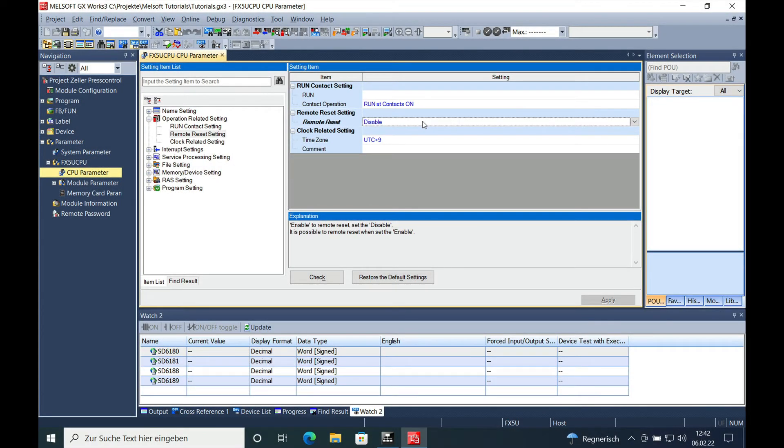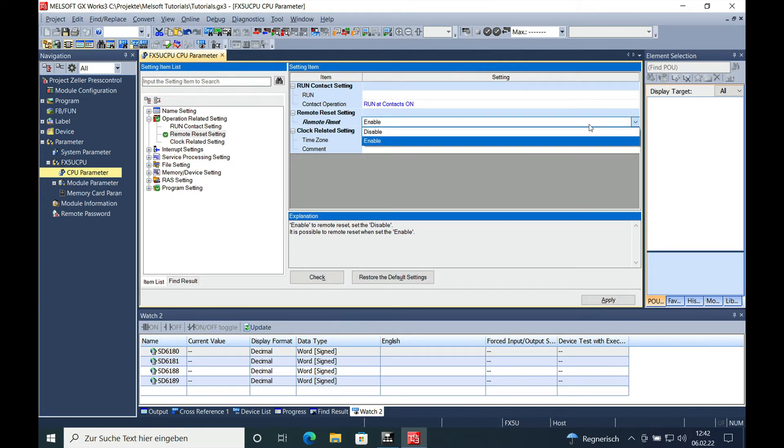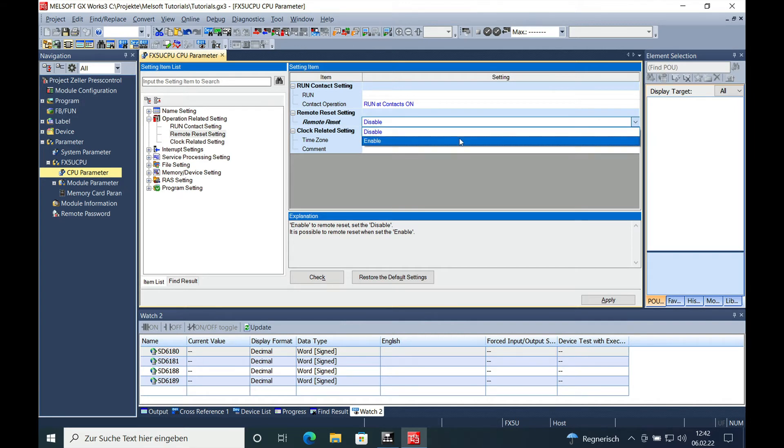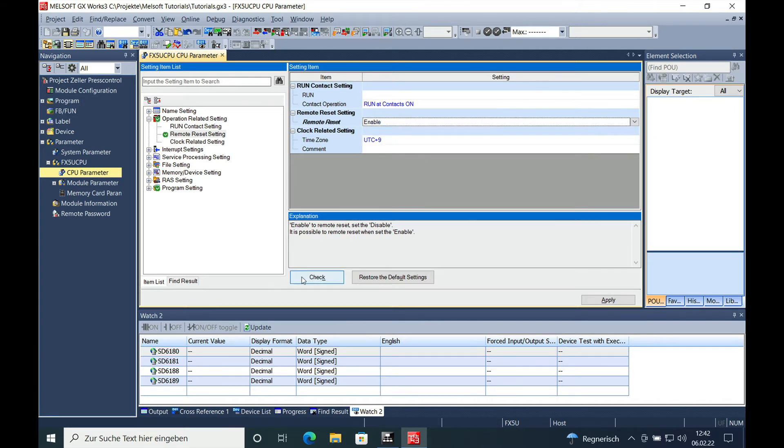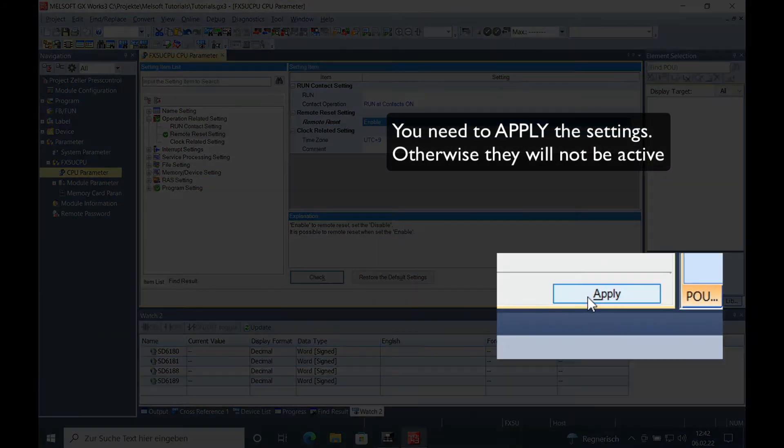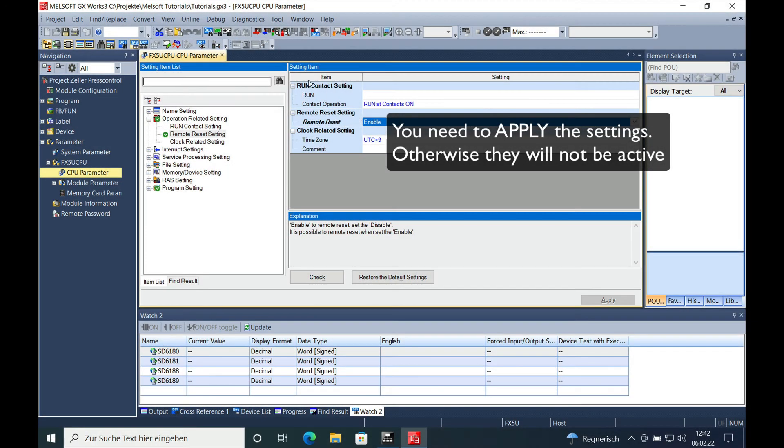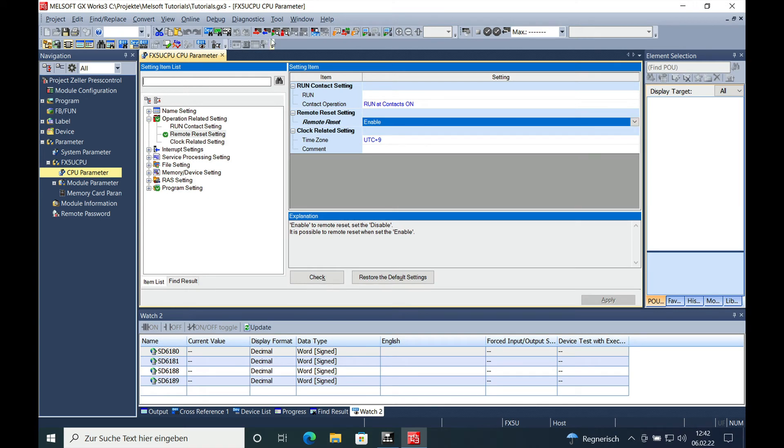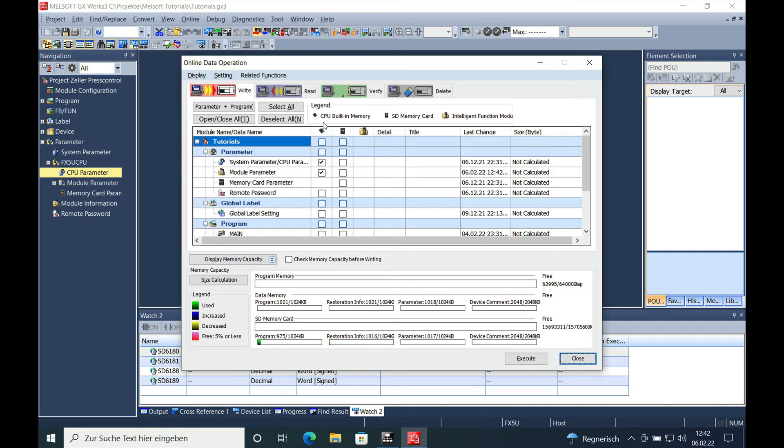You can change the remote reset setting on here, either via a double-click or on this little arrow right here, and then make this Enable. Check your parameter, which will be okay. Apply—don't forget to apply it, otherwise the change will not be active—and then download it.